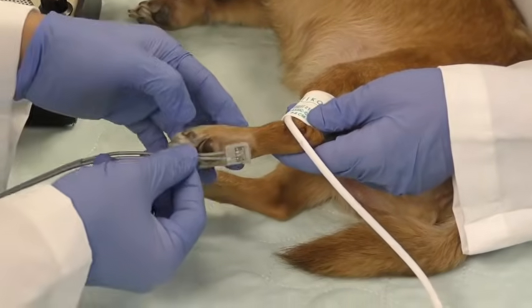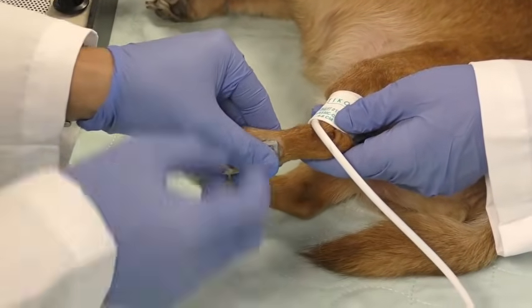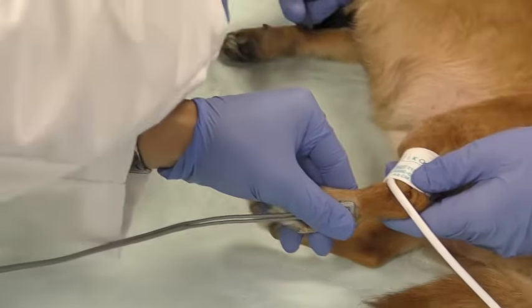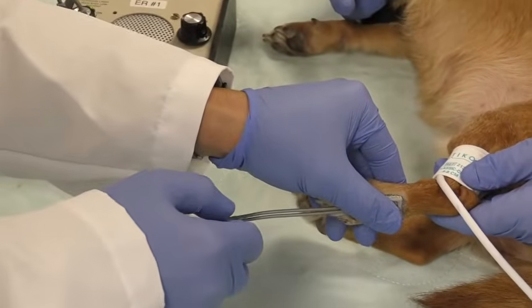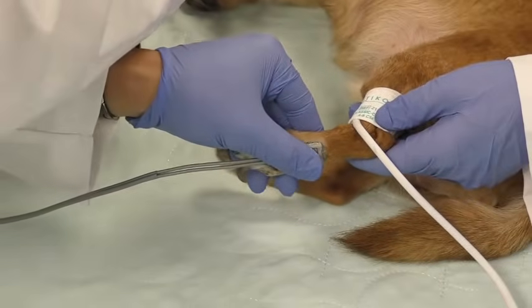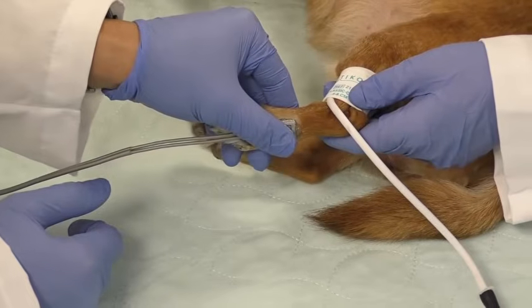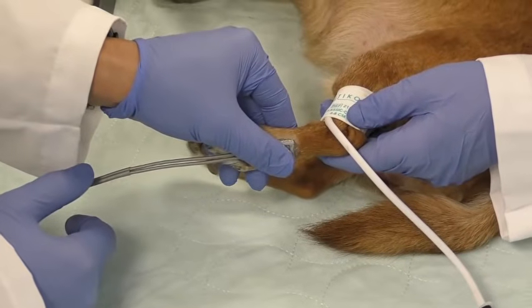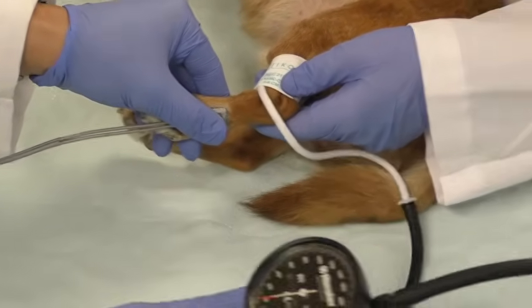The Doppler uses two piezoelectric crystals to detect blood flow through a peripheral artery. The crystal is placed over the side of the artery, distal to the appropriate size pressure cuff. The Doppler emits ultrasonic waves toward the tissue, which then reflect back to the probe. These ultrasonic waves are converted to audible arterial sounds.